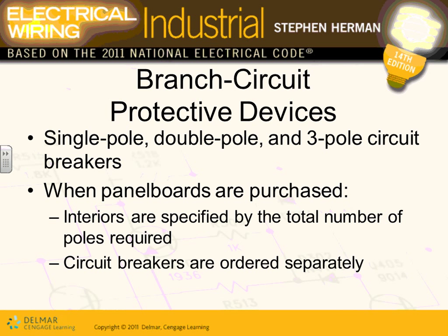When you purchase the panels in commercial industrial, you're going to hear, when Square D and Cutler-Hammer came here, if you guys remember, I know it has been a while, that contractors always buy the frame, the panel, and then the chassis inside the panel comes later. So they buy a box that can house 400 amp. You put the box in the wall or on the wall, surface mounted typically. You put your pipe, your electrician comes, pulls your wire and everything else. Then later on in the project, you order the chassis, the stuff inside it, the cover, and you attach it right inside that box. And then the circuit breakers.